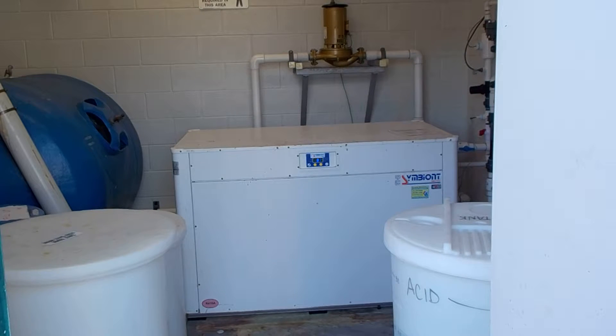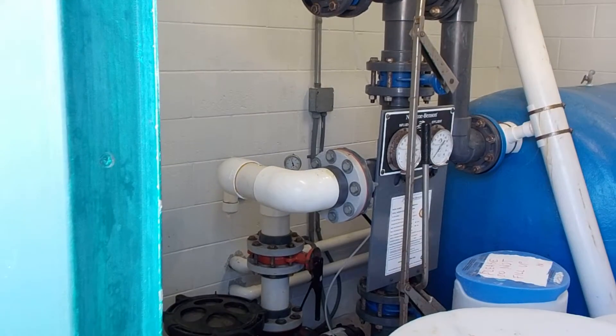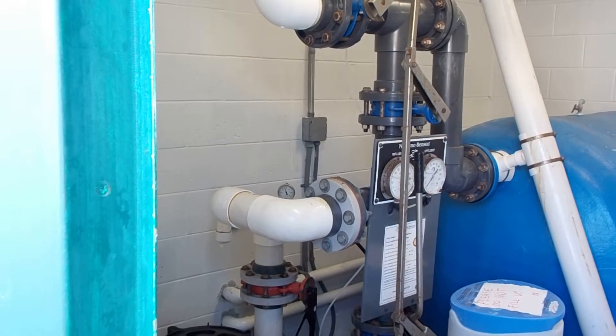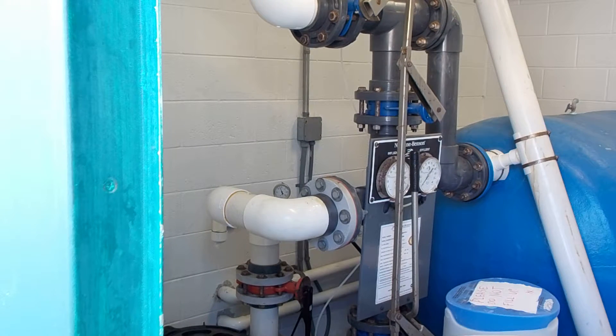Of course, that's going to trigger the autofill because we lost a portion of the water. What I want to do now is point the camera on those gauges and see. That's going to take a few minutes because one thing that happens is during the backwash the pumps run at 100% typically, versus during normal operations they would only run around 80%. So it's going to take a while for the power to come down to the level we operate at in regular operations.